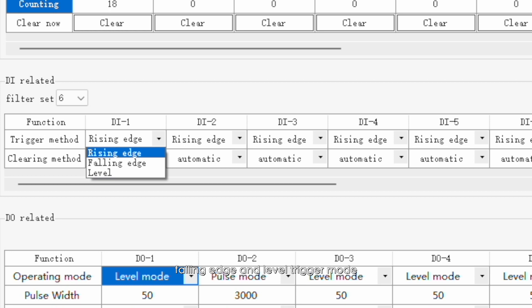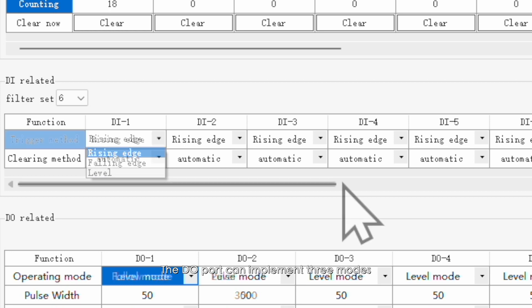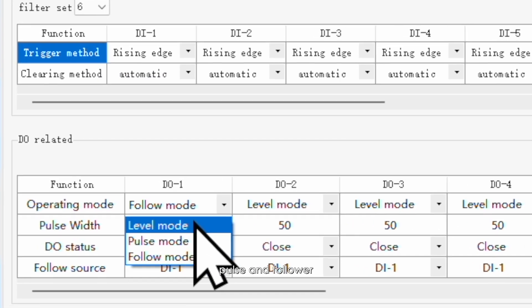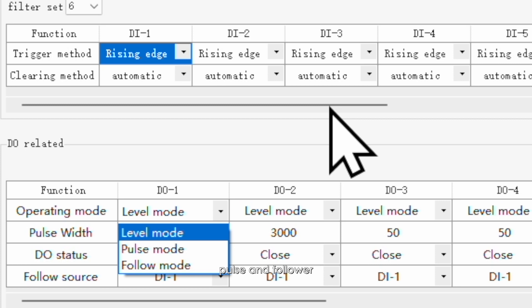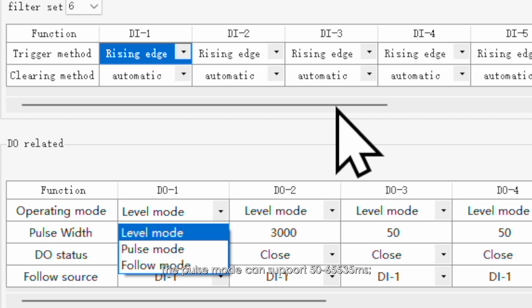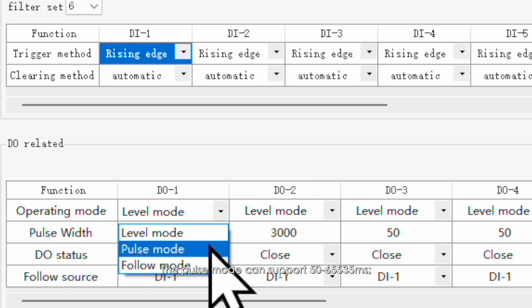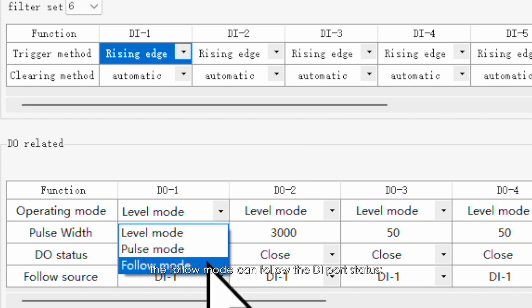The DO port can implement three modes: level, pulse, and follower. The pulse mode can support 50 to 65,535 milliseconds. The follow mode can follow the DI port status. The level mode can be switched manually after saving the settings.